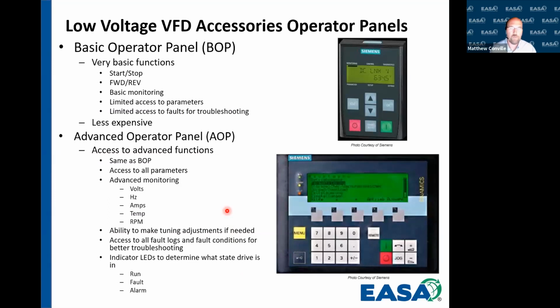So let's talk a little bit about operator panels. There's two basic types. You're going to have a basic operator panel and an advanced operator panel. Basic operator panels are going to give you very basic functions, just like their name calls. Start, stop, forward, reverse. You might be able to do some very basic monitoring. You really won't have a lot of access to the parameters of the drive. You can do very simple setups, but you're going to have very limited access for faults for troubleshooting.